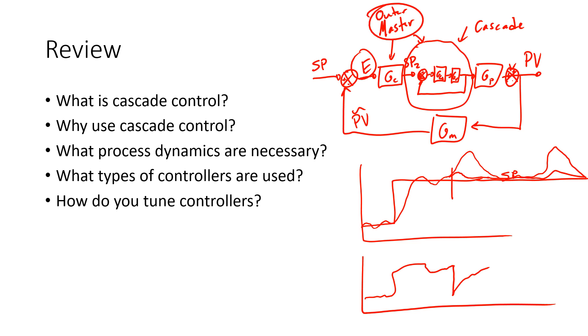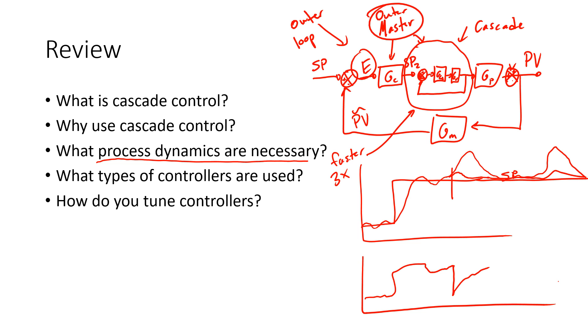We're also going to talk about the process dynamics that are necessary. This inner loop has to be much faster than the outer loop. We typically want it to be about three times faster than the outer loop in terms of following the set point, and we'll show you an example of why that's the case. We'll also talk about what types of controllers are used and how to tune these cascade controllers.